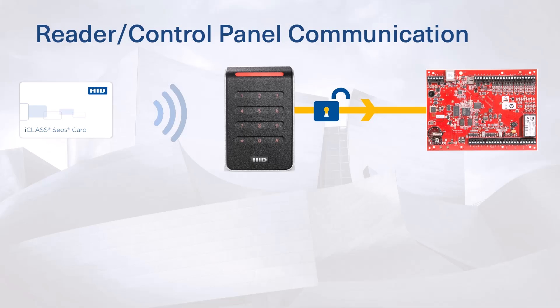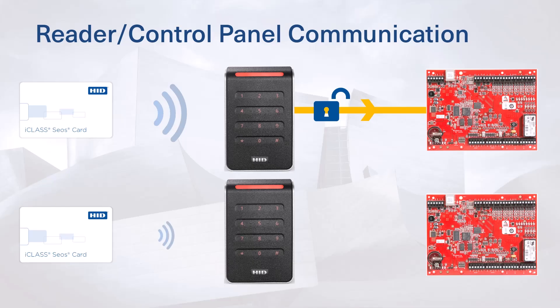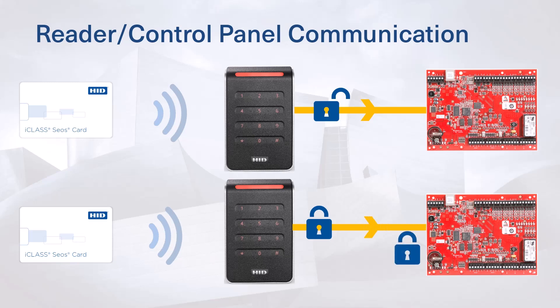Open Supervised Device Protocol, or OSDP, is an open standard utilizing RS-485 to enable bidirectional communication, enhanced security, and other advanced features between readers and control panels. The bidirectional interface enables administrators to manage all reader functions centrally, including reader audio-visual responses, configuration changes, firmware upgrades, and status monitoring.